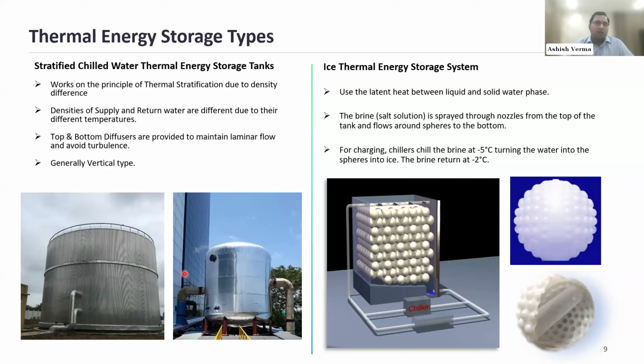The left-hand side is the regular thermal energy storage tank, which is used in the district cooling plant. The right-hand side is a smaller tank, which is mostly used as a backup, mostly in the data center industry, where they need backup in case there is a power outage and the chiller goes down and the DG has to be started. So there's a time lag. For that particular duration, these smaller thermal energy storage tanks are used.